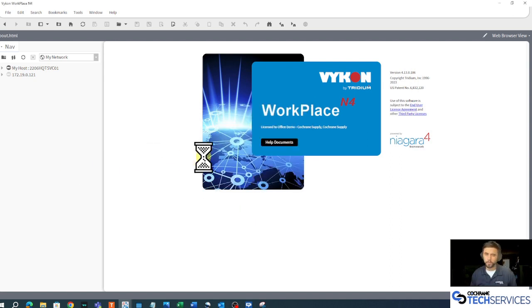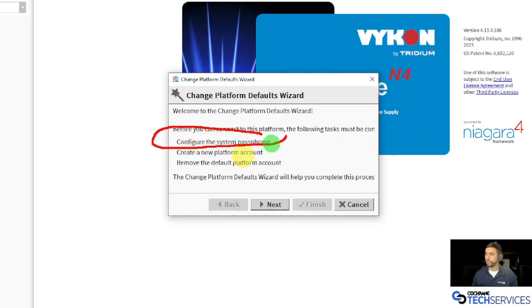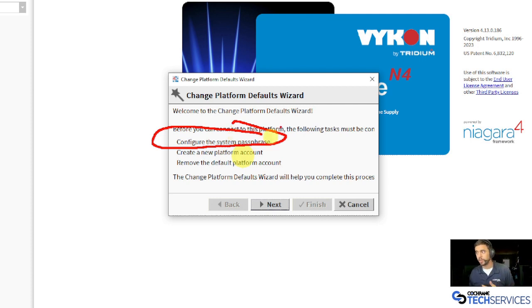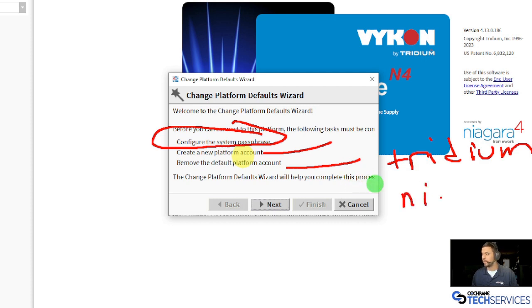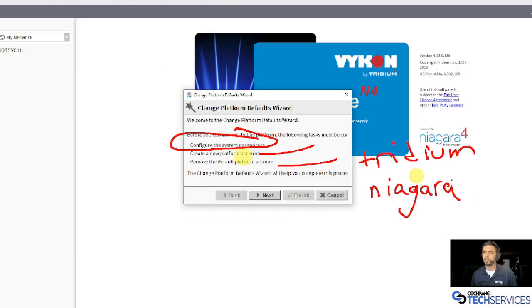Before we can really access that platform, by default we're going to have a few tasks to complete. The first task is to configure a system passphrase. That will protect sensitive data within our Jace — for example, if our Jace is talking to a supervisor using credentials and somebody hacked it, we don't want to give those credentials up. We're also going to remove that Tridium Niagara account and replace it with better credentials, since it's public knowledge that Tridium Niagara is the default and we should certainly change it.